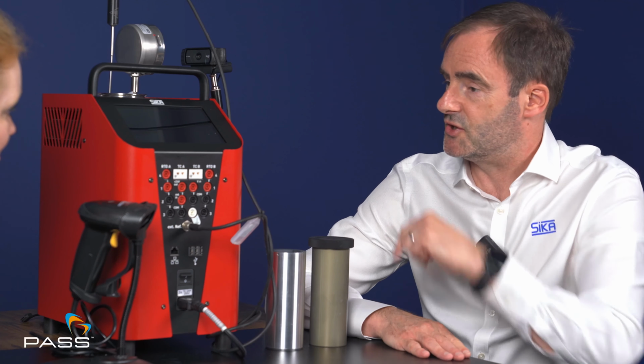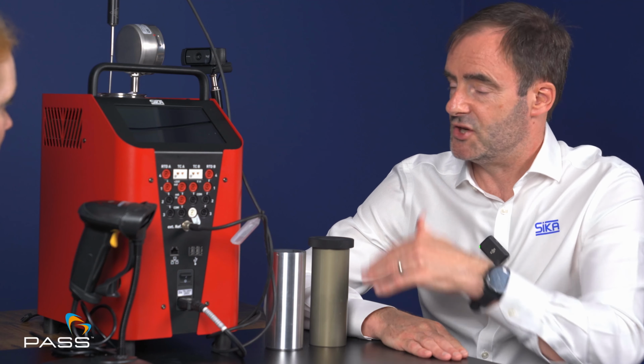And then what happens is once the user has set up the devices under test and the calibrator itself, you can actually just power it up, switch it on, and it'll run through its calibration process all on its own and then finish at the end. You don't have to stand over it. You don't have to do anything with it. And at the end of that process, you'll receive a PDF calibration sheet.